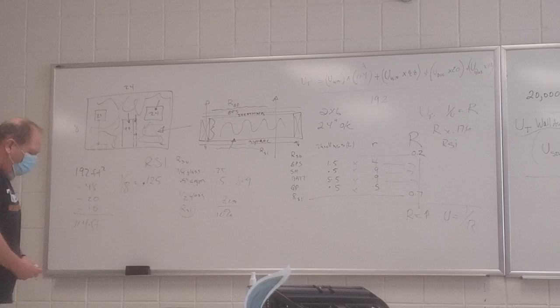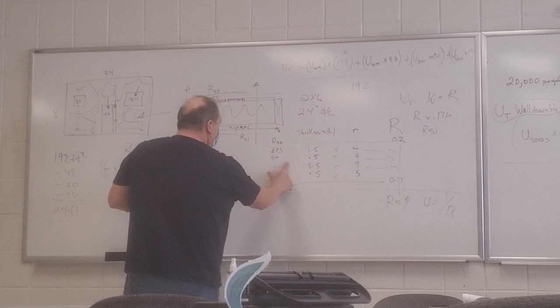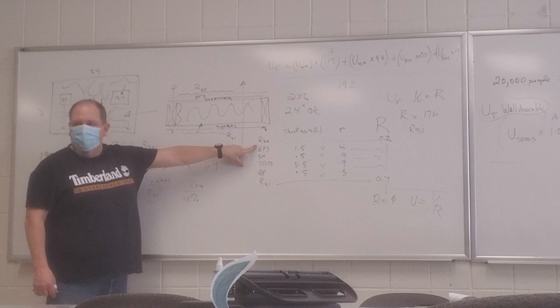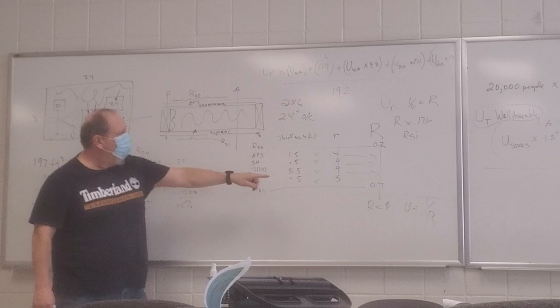So I know today I just went through this. You're evaluating the stud first. It doesn't matter which one you do. So what I did, I went through the stud first. Remember, on the outside, there's a surface film resistance. That little strip of thin air that's still. It provides some R-value. Not very much. 0.2. You've got to know that.